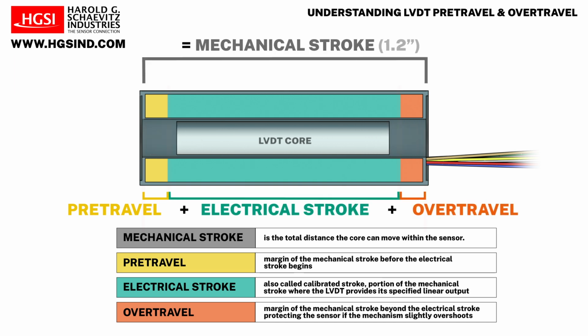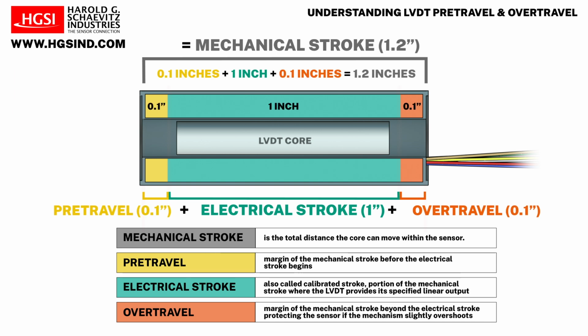For example, if an LVDT has a total mechanical stroke of 1.2 inches with 1 inch of electrical stroke and 0.1 inches of pretravel and overtravel on each side, only the center 1 inch provides accurate output. The 0.1 inch margins are safety zones.